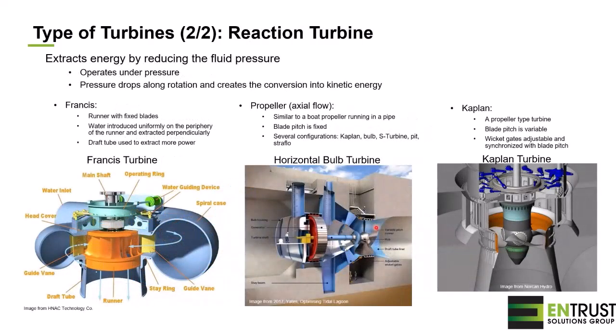On the side of reaction turbines, we find Francis turbines. A Francis turbine has a runner with fixed blades. The water is introduced uniformly around the periphery of the runner by way of a spiral case that will distribute the pressure equally, and the water will drop significantly in pressure by passing through the runner. We can use the draft tube to extract even more power.